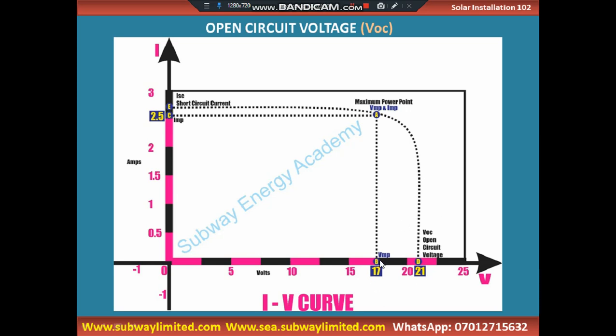If you look at this point, we are having voltage at maximum power to be 17 volts and open circuit voltage to be 21 volts. Remember we said that a 12-volt solar panel will always give you this range, and this is what you might likely have as the open circuit voltage on the nameplate and the voltage at maximum power equally on the nameplate.